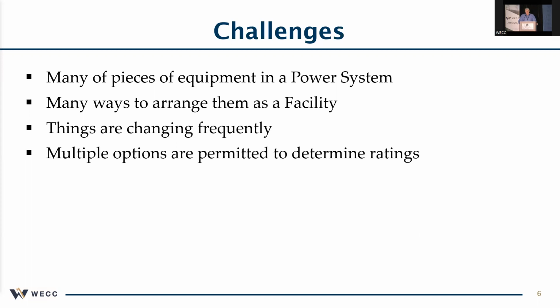But anything that can be removed, that can be unbolted and taken out of a power system, technically should have a rating to know if it can carry the current that it was intended to carry when you put it in there. That's bus links, breakers, wave traps, jumpers, everything. So there's a lot of stuff to keep track of, and there are many ways to arrange them. You get all this equipment together, and now you can put it together in any sort of arrangement: parallel connected, series connected, shunts. All this stuff comes into play when you're trying to determine what your facility ratings are.